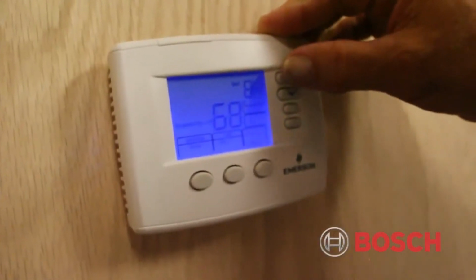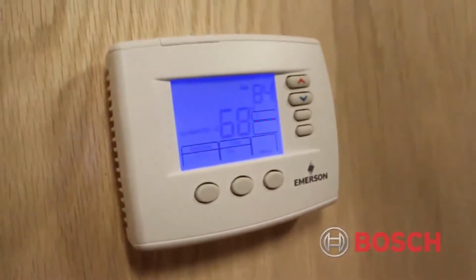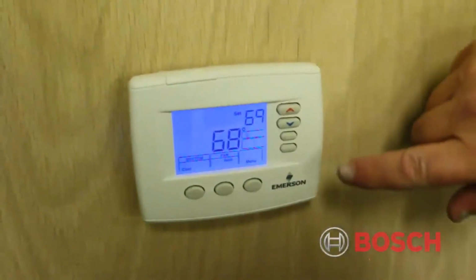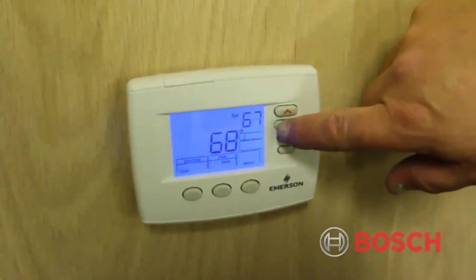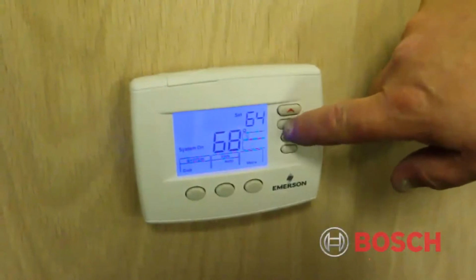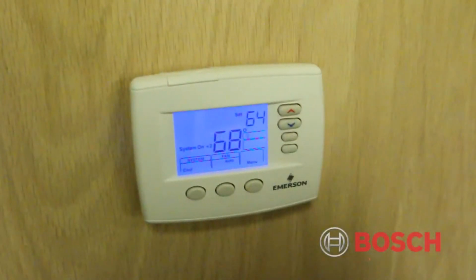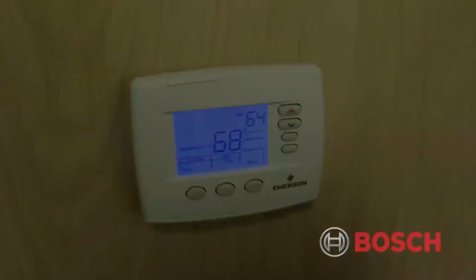And then once power is applied to the unit, the thermostat must be configured for the number of stages that you need for the TAO25. So always consult the installation instructions that come with the control to program the stat, and consult the installation instructions that come with the unit to make sure you wire it correctly.